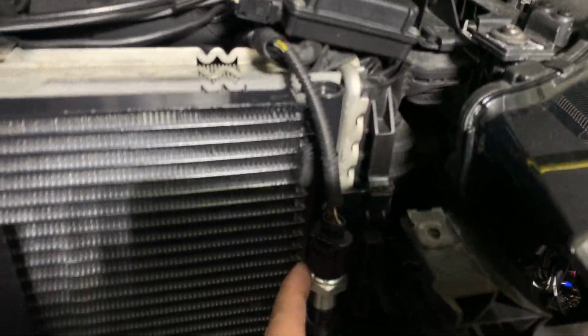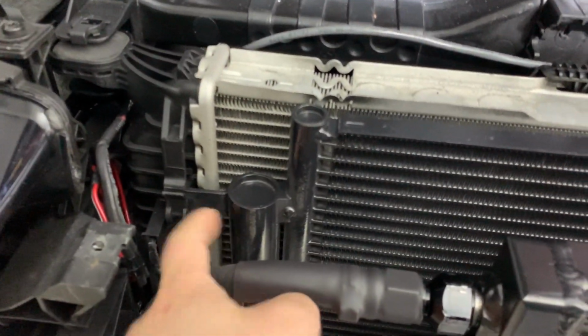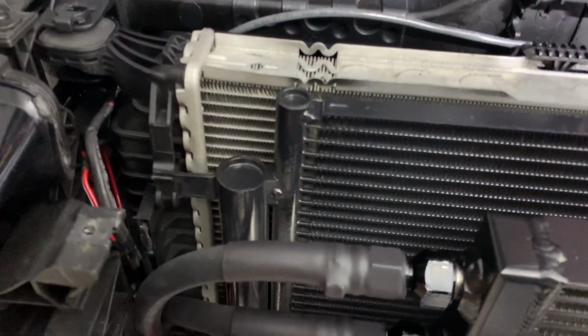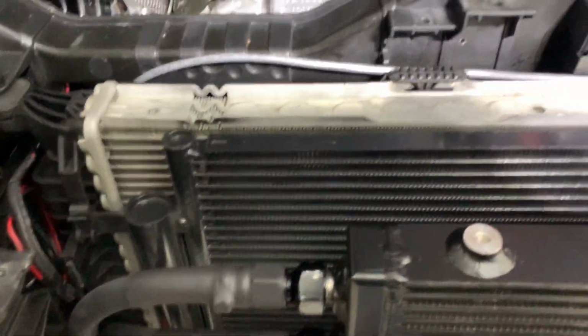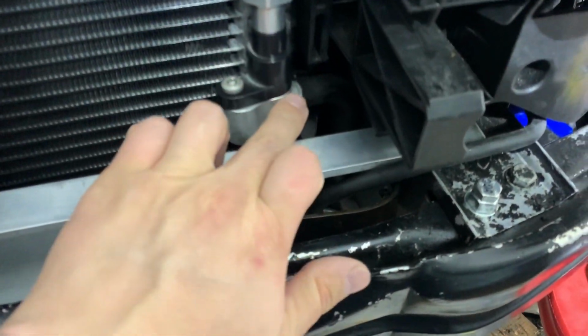Sensor, make sure it's all good. If you have a dryer filter and you're keeping the old one, take the dryer filter out and replace it - absolutely, no matter what, you have to replace that. Check the sensor, check all the connections, all the O-rings on the connections, make sure they all seal and are tight. This is very important for preventing freon leakage.